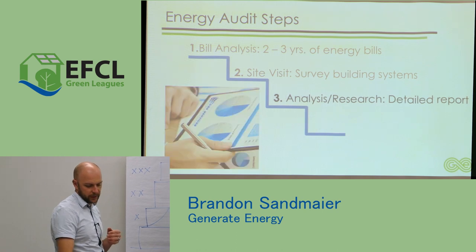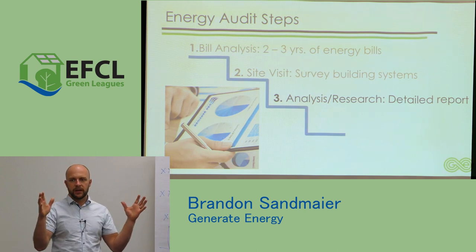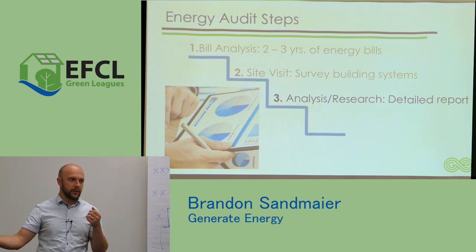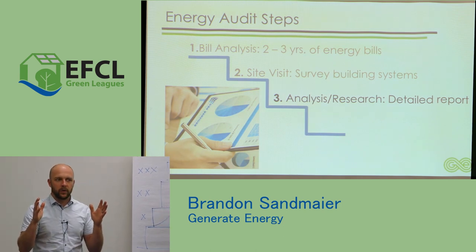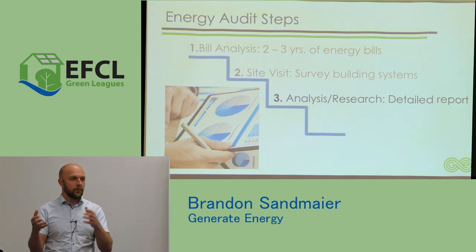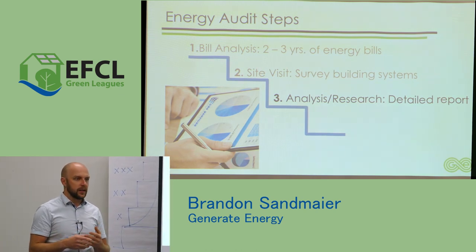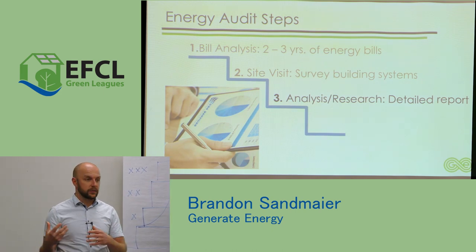Sometimes we actually contact manufacturers. I know Ridgewood had a huge dimmer system for their lights because they have a beautiful hall, like a wedding hall, with massive pendant lights that they would want to dim for the first dance or whatever. But the dimmer pack wouldn't work with the LEDs, because you have to actually change your dimmers, like you do at home. It's the same concept, but we actually had to get in contact with the manufacturer and discuss the viability of changing them out to LEDs. And it didn't make any sense in the end because the costs would have been really high. They would have had to actually replace this unit.